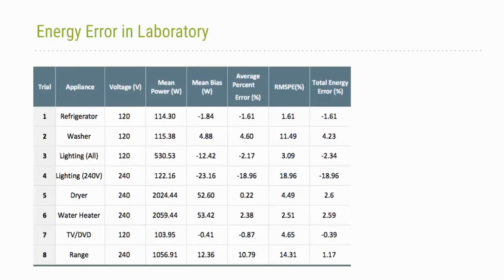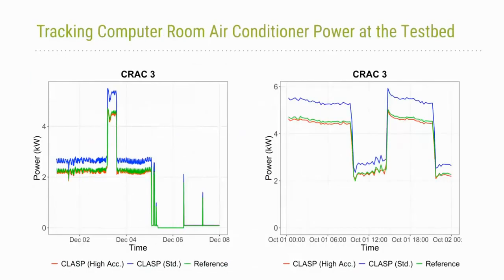This is testing some fluctuation and part load performance of the CTs, so that their actual specification might be less than 1% error, but you end up seeing a little bit more than that because the load is fluctuating and it's a slightly different test environment than the ANSI rating system that the CTs are tested under in laboratory environments designed for testing accuracy. So this is more of a live demonstration of the technology, but in a laboratory environment. But they performed quite well here, so they continued on to the field testing, and so that's the next slide, I believe.